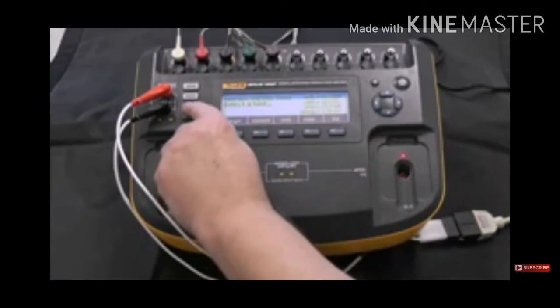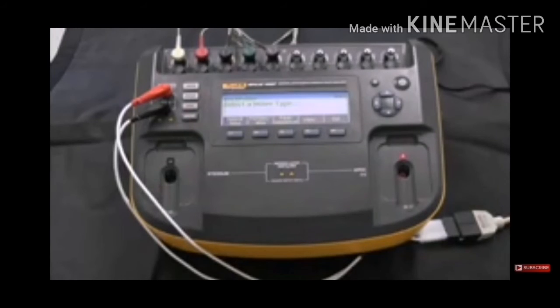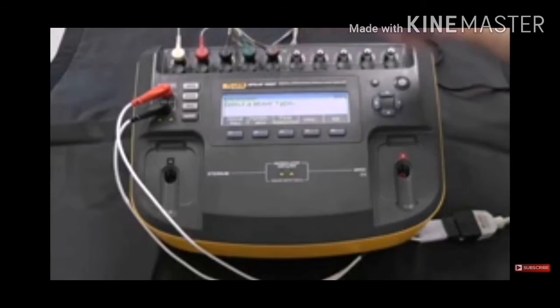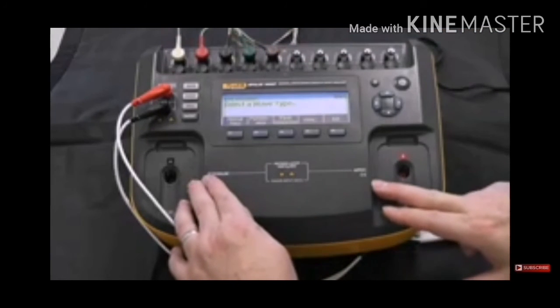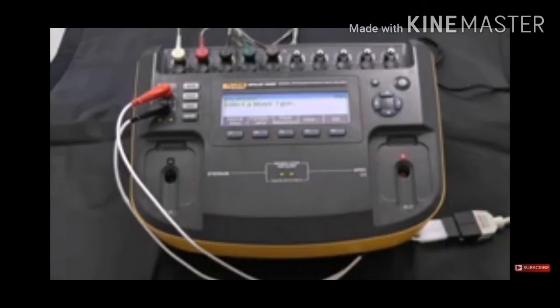All right, ECG. The ECG waveforms are simulated waveforms that are delivered through the lead wires, and they're also delivered through the pads or paddles connections. So we have a variety of different categories of wave shapes that can be displayed and sent to the patient monitor part of the defibrillator. And this is important when you're going to do AED testing. So you can select a whole lot of different arrhythmia waveforms here. We're not going to go into all of them right now.